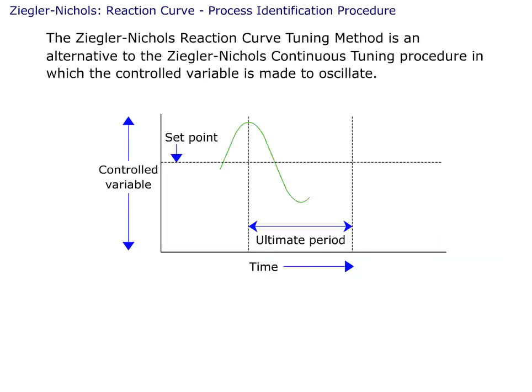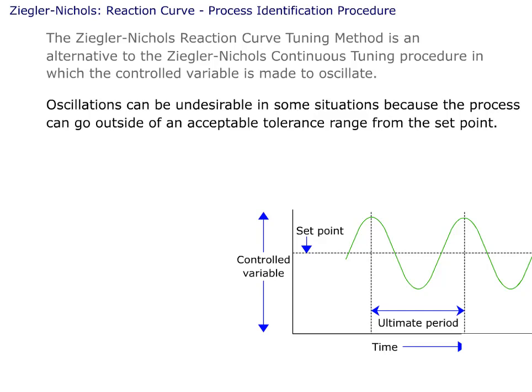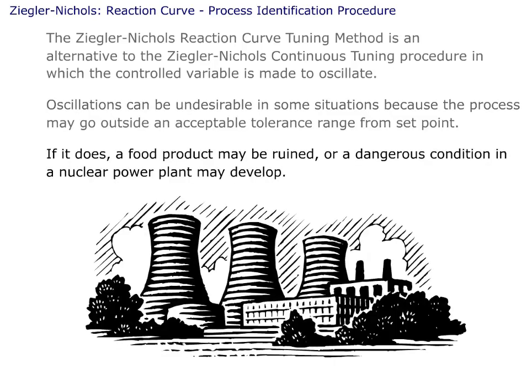The Ziegler-Nichols reaction curve tuning method is an alternative to the Ziegler-Nichols continuous tuning procedure, in which the controlled variable is made to oscillate. Oscillations can be undesirable in some situations, because the process can go outside of an acceptable tolerance range from the set point. If it does, a food product may be ruined, or a dangerous condition in a nuclear power plant may develop.